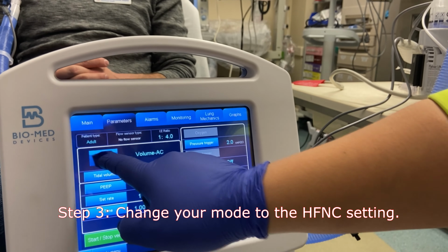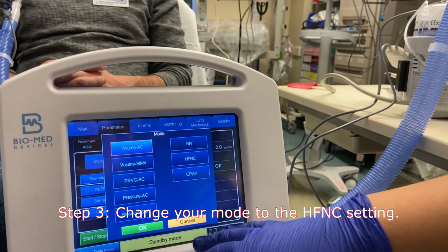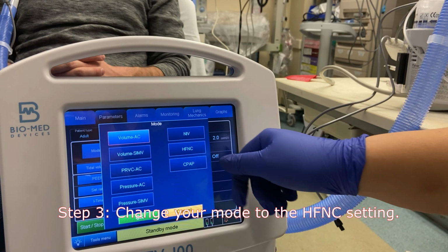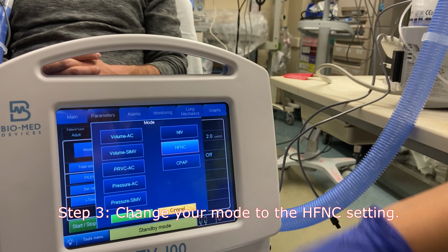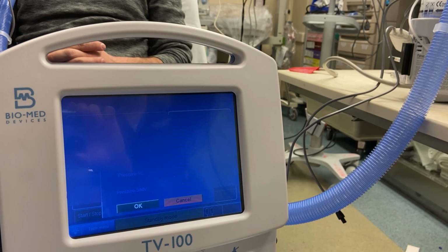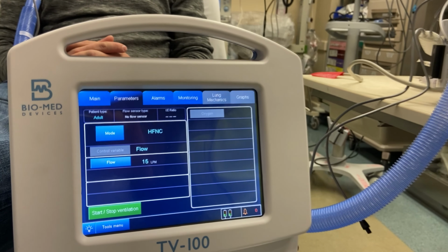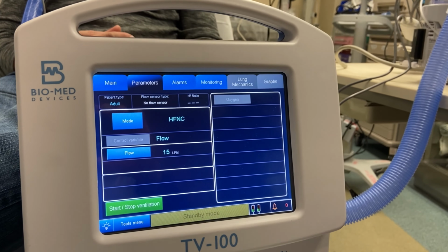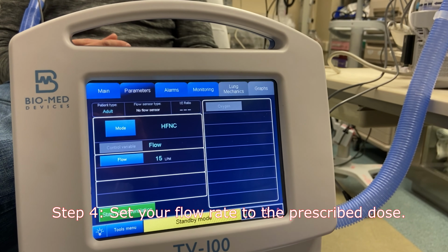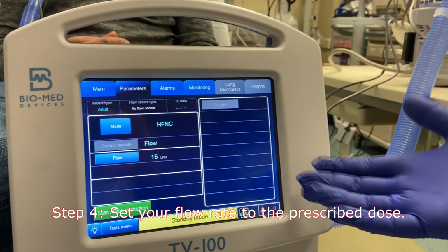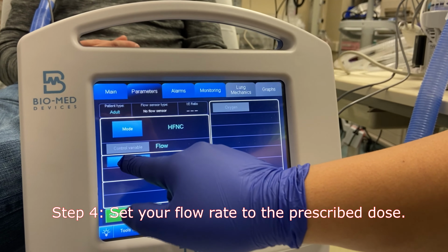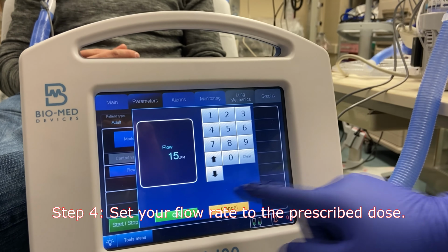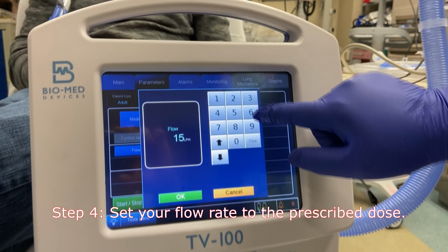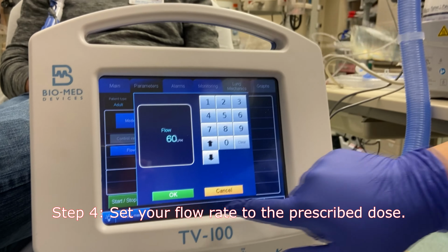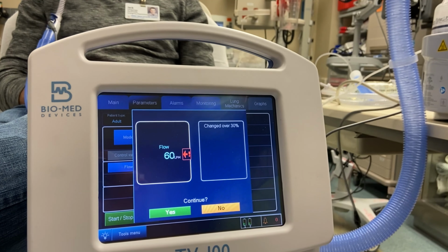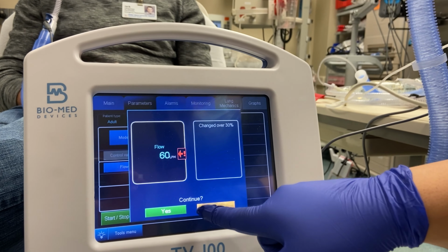So here we are, mode. And these are all your settings. And we're going to go to high flow nasal cannula. And then hit OK. All right, so now you're at the main screen. So your flow rate, whatever the prescription will say, we're going to be starting mostly at 60 liters per minute. So you're going to go to flow, and then your flow is set to 15, but you could change it. So 60, and then OK. Continue. Yes.